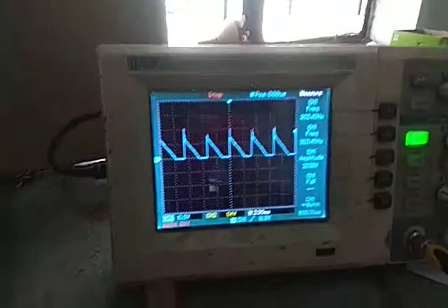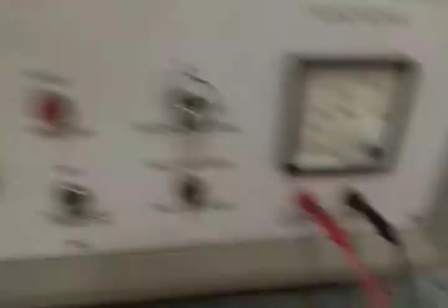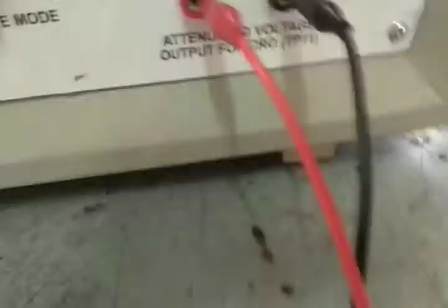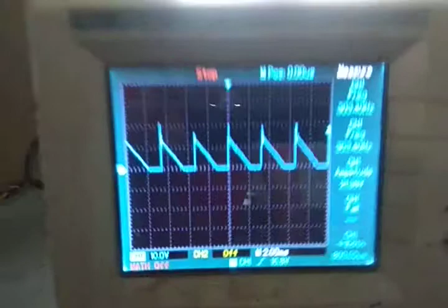Being a three-phase fully controlled converter, the proof is that all 6 thyristors are working properly. I will put this in full wave mode and switch on the CRO. I have connected output across this TP11, and I have now stopped the DSO in stop mode, so I am capturing and scrolling that image. Now I can see the time difference between any two successive pulses is 3.3 milliseconds.